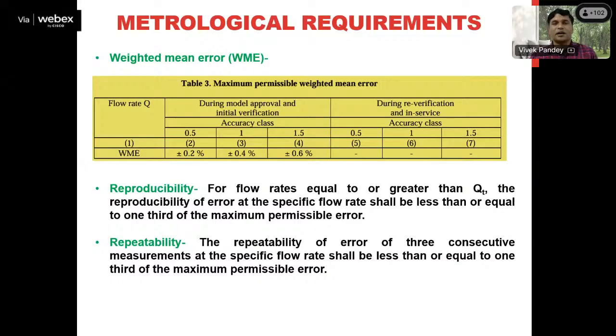Now, these two parameters are also very important with respect to the accurate functioning of this measuring instrument. So what is repeatability? Repeatability in context with the gas meter is how consistent your gas meter is with respect to the measurement of the quantity of gas. That means suppose a gas meter is there and the flow rate specified by the manufacturer is, say, 100 liter per hour to 500 liter per hour. This is the range of the flow rate. Minimum to maximum flow rate is specified by the manufacturer.